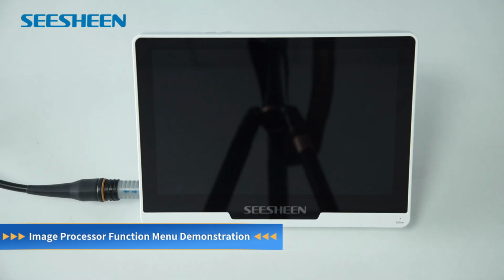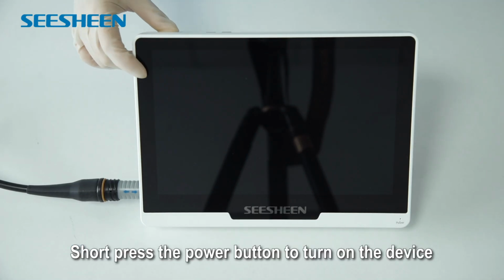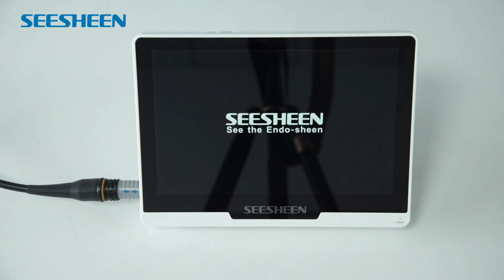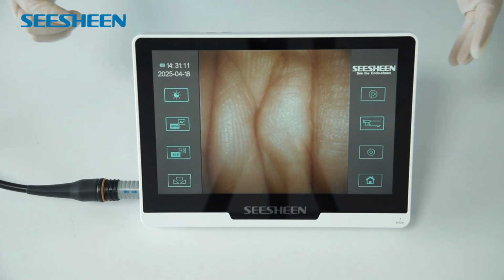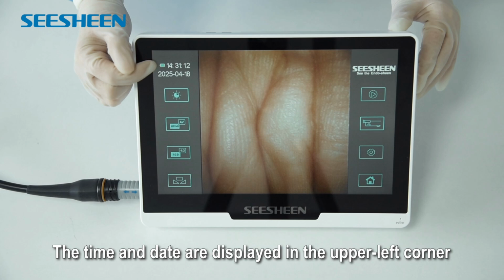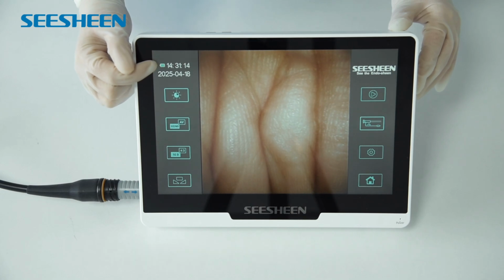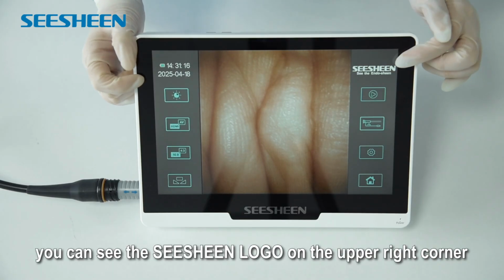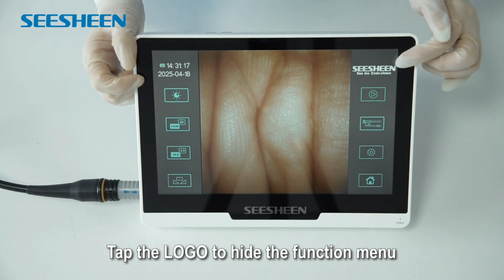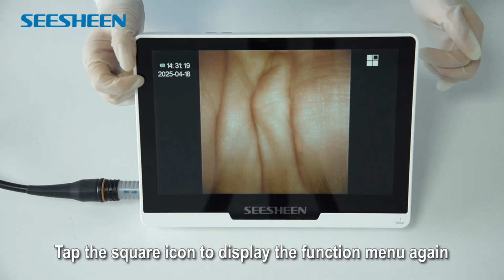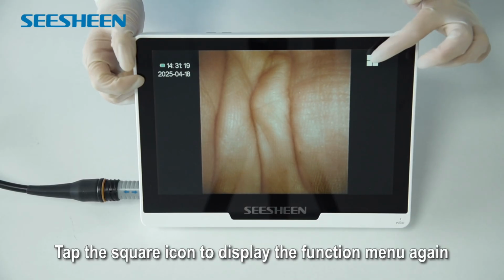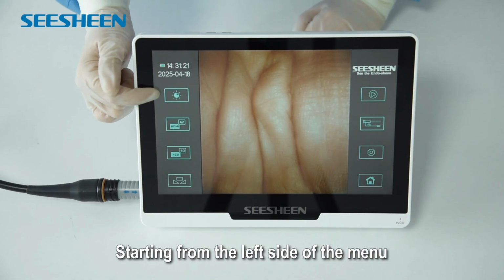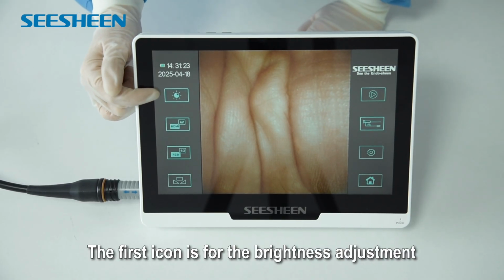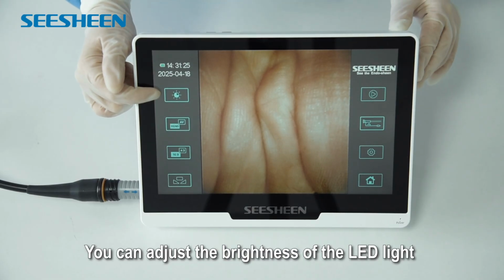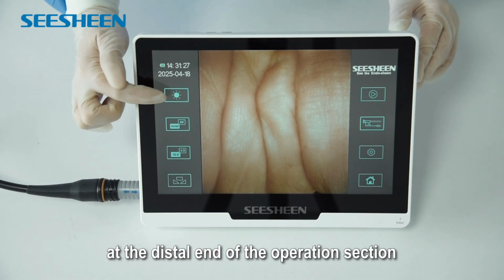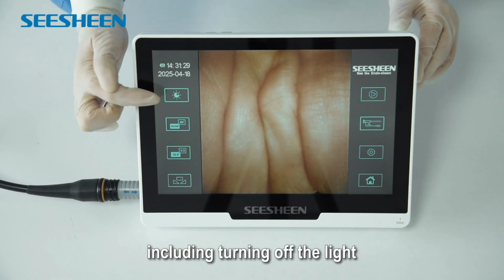Image processor function menu demonstration. Short press the power button to turn on the device. After the image appears, the time and date are displayed in the upper left corner. You can see the Seesheen logo on the upper right corner, which is a function hidden button. Tap the logo to hide the function menu. Tap the square icon to display the function menu again. Starting from the left side of the menu, the first icon is for the brightness adjustment. You can adjust the brightness of the LED light at the distal end of the operation section, with 4 levels of brightness, including turning off the light.